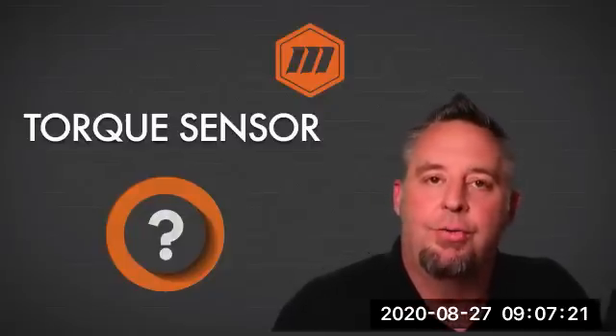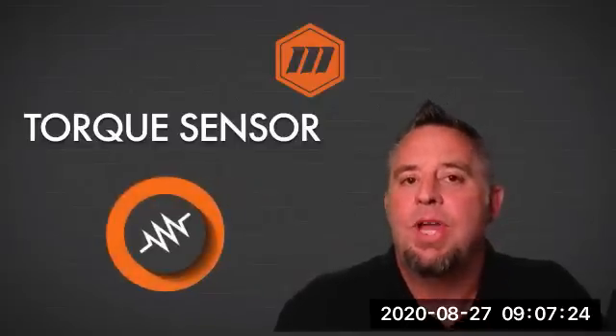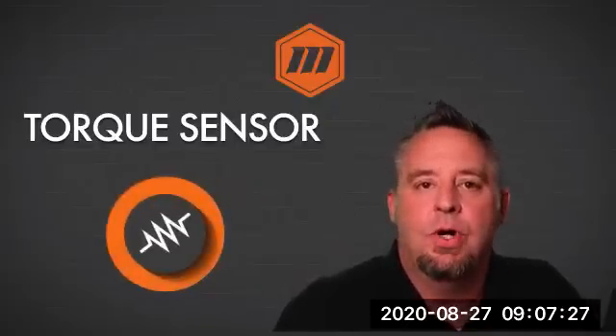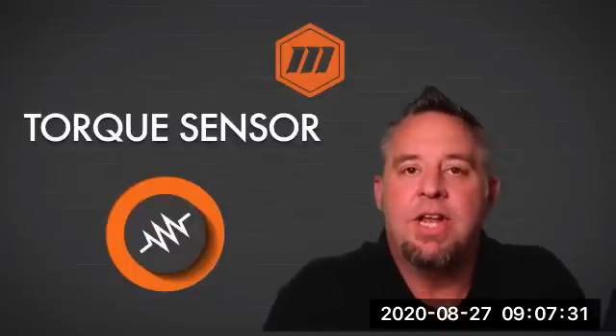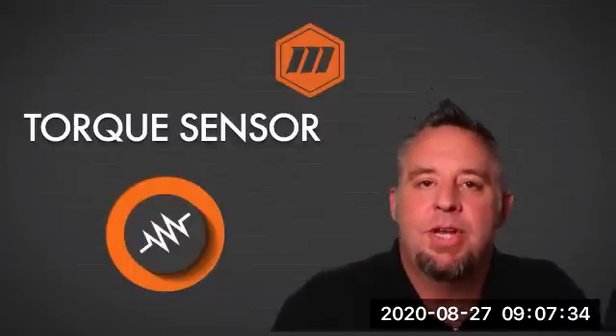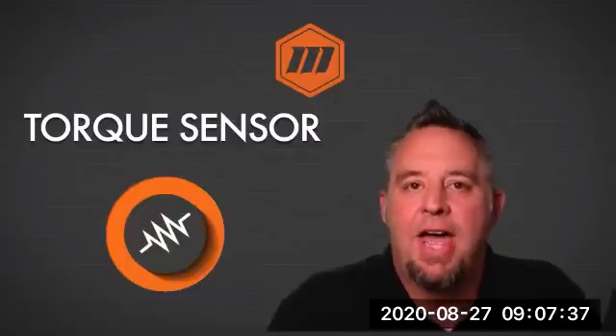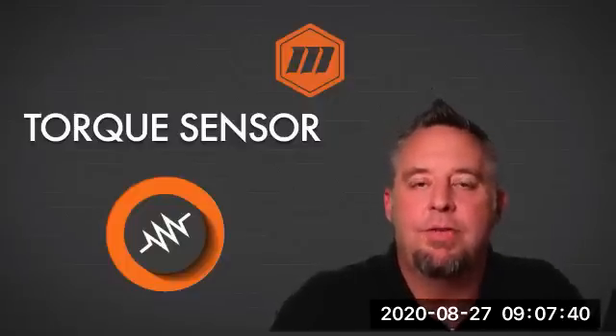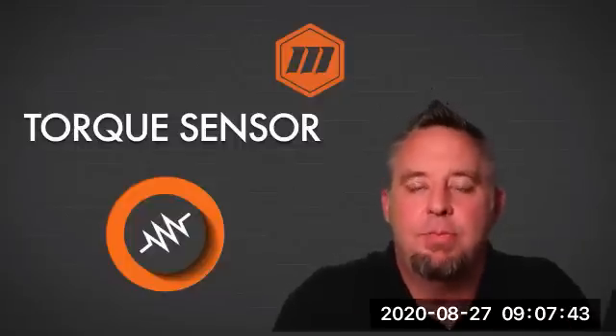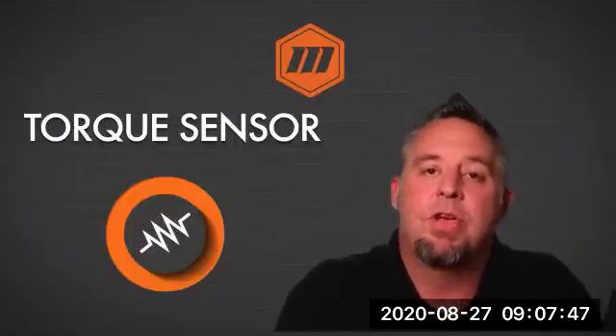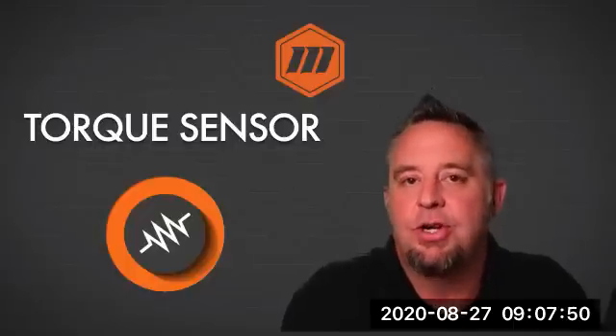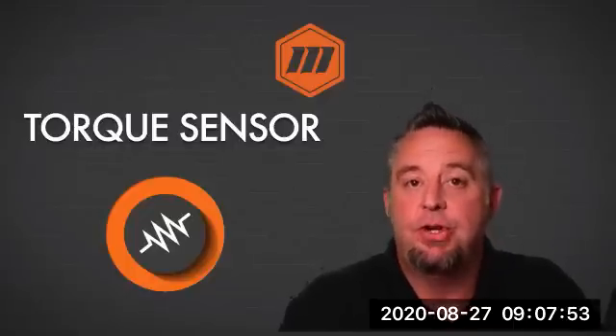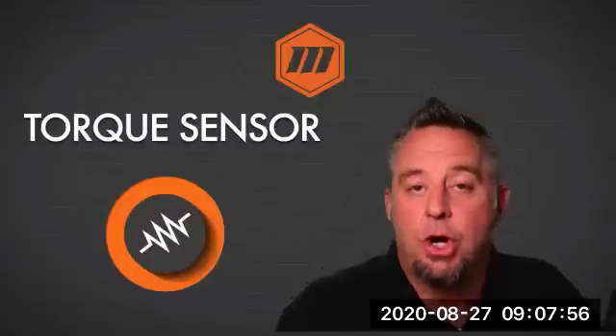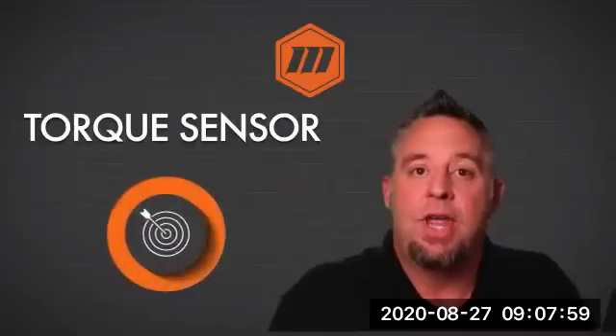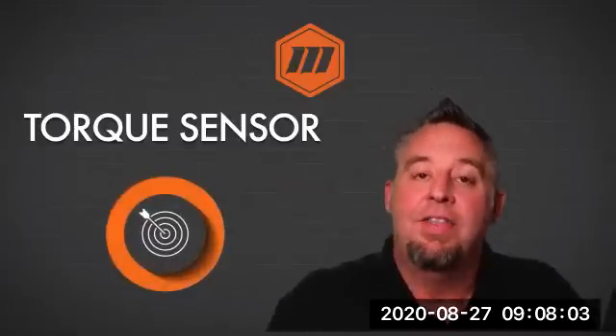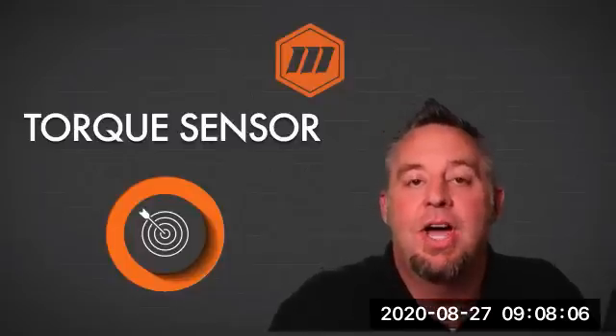Well, they're really torque transducers, and they're primarily giving us the data through the measurement of resistance. And we'll talk a little bit more about that closer to the end of the presentation, but it basically gives us the ability to take an analog signal, convert it to a digital form that is extremely accurate, and then give it to us through our torque analyzer. So the package, the way that it comes, we have our torque sensor, and then that sensor is married or paired to a torque analyzer.